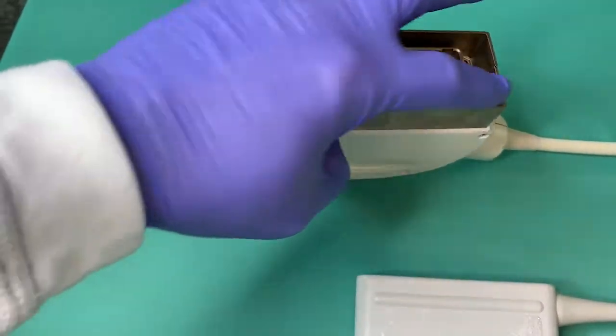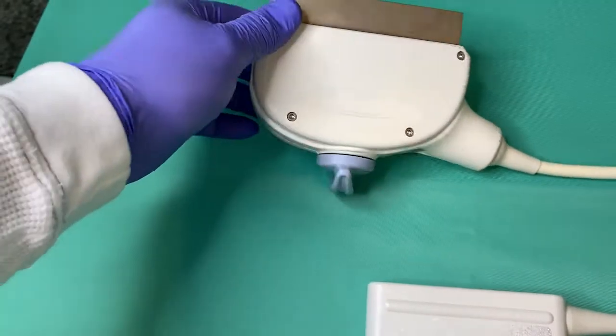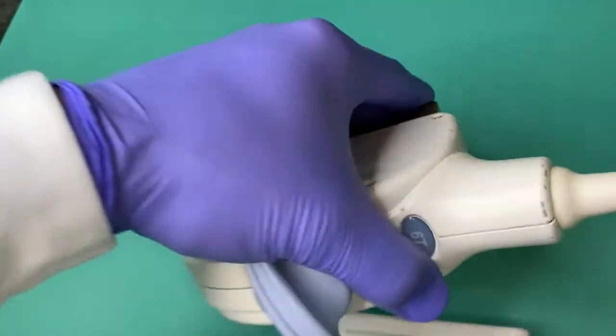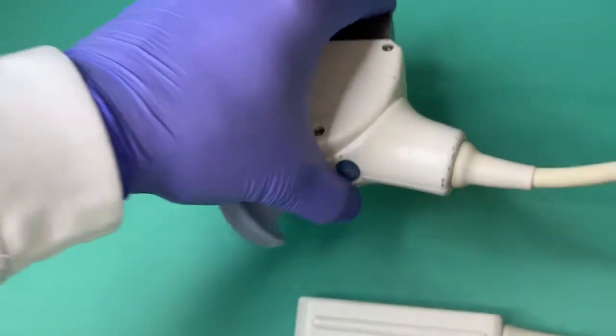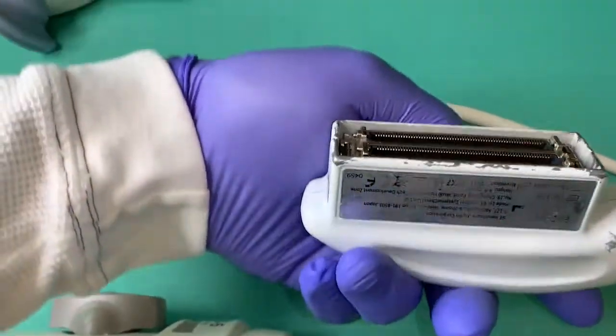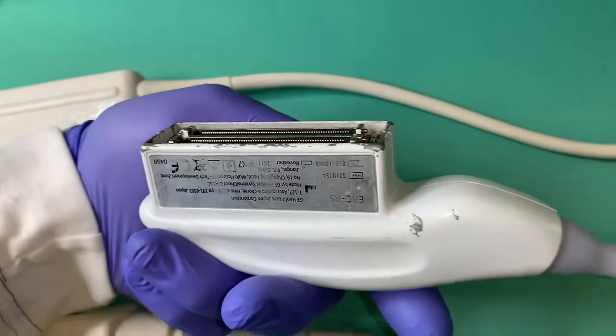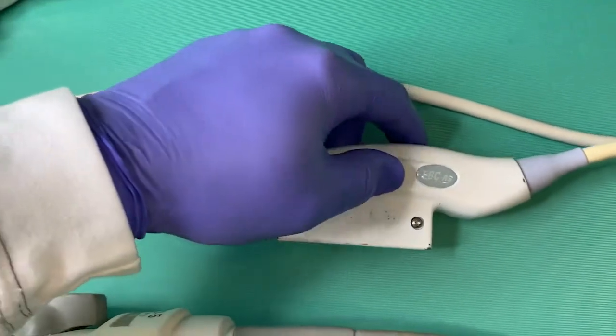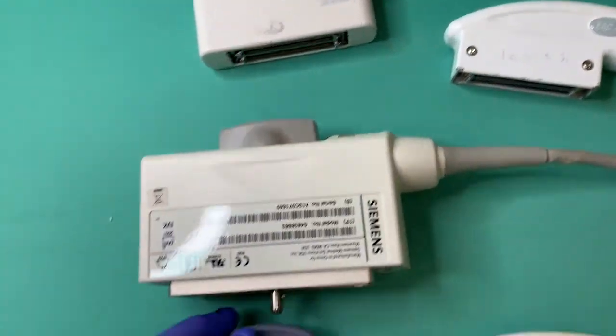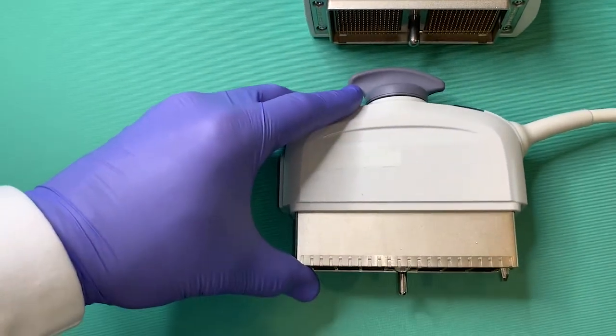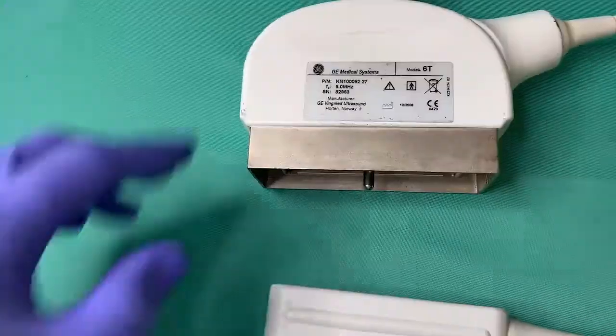It's common for the paint on the connector housing to become chipped over time, and it is indicative of some level of trauma. More important is to examine the shape of the housing, inspecting for any deformations. Deformation may make the connection to the scanner challenging and may lead to intermittent performance issues.